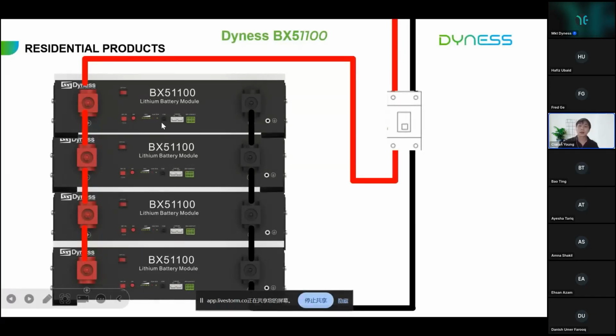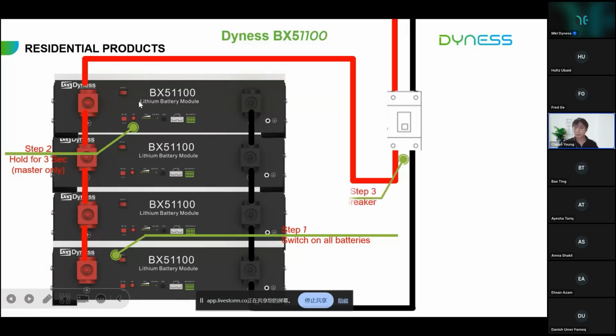When you want to turn on the battery, you have to switch on all the breakers on the battery. Next, hold the switch button of the master battery for 3 seconds - attention, only the master battery. Then you can turn on the breaker between them and the inverters.